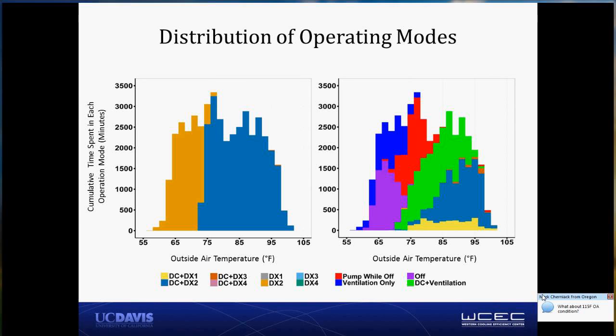Note also that there's this red blip in the top, in the middle of the chart. This is a funny mode that we've observed on a lot of the dual cool units when the pump runs while the entire unit is off, which isn't very effective, and amounts to a little trickle of energy used to circulate that pump. But it can account for, in this case, hundreds of hours over the course of a single month for some units. So we see that as one small opportunity for improving the system, maybe through some integrated control schemes.